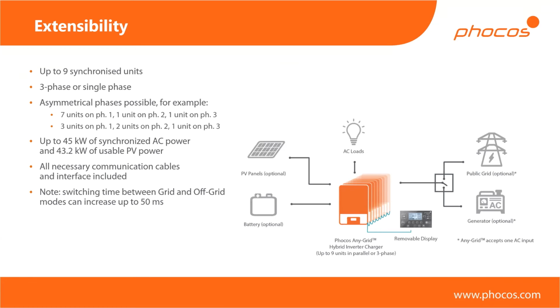Or we can hook these up in 3-phase. And even if we hook it up in 3-phase, then we can even choose asymmetrical phases. So an example I give here is we might have 7 units on phase number 1, and just a single unit on phase 2, and a single unit on phase 3. And this might be a reasonable scenario if you're working with a large home, for example. You might have a lot of single-phase loads, but you'll have a couple of 3-phase loads. And you have those last 2 inverters just there for those, like your circular saw and maybe your oven, which might be typical 3-phase devices that will be running on these other 2 inverters. And all of your single-phase devices will be connected to the first 7, which will give you plenty of power on that single phase. Of course, you can also have symmetrical phases.